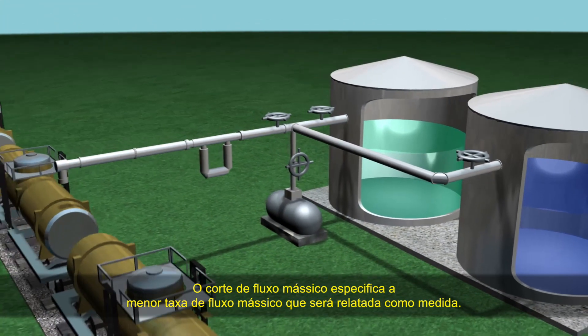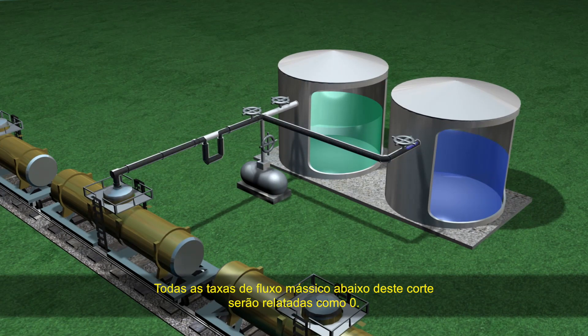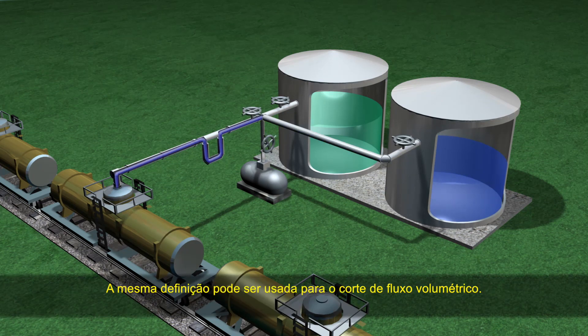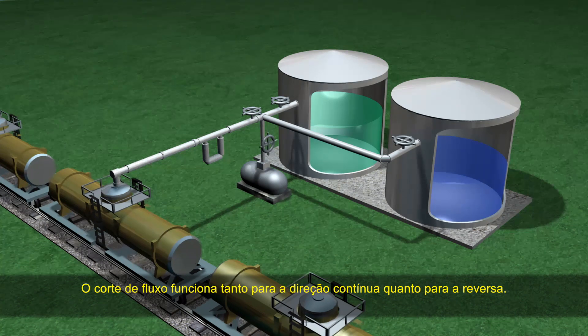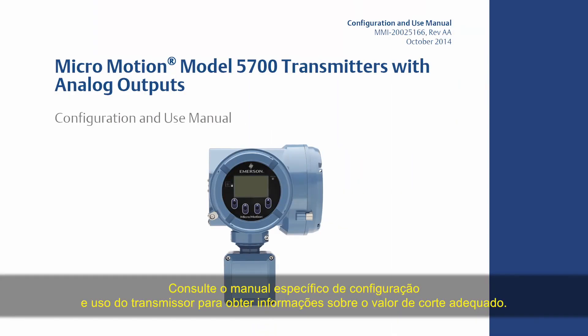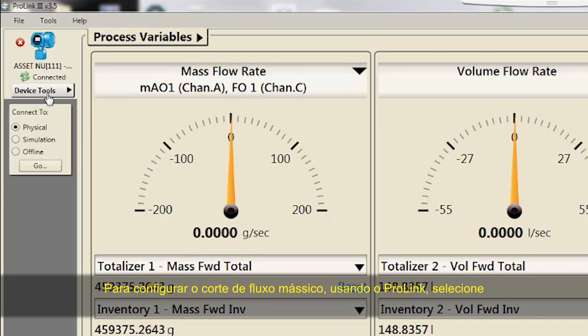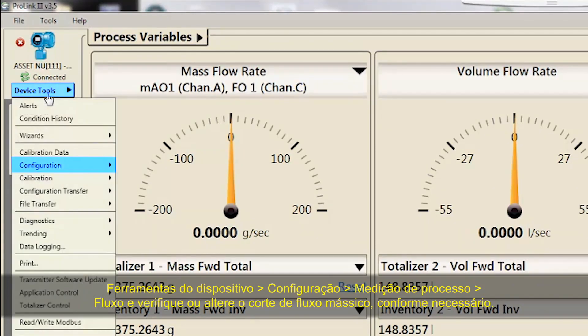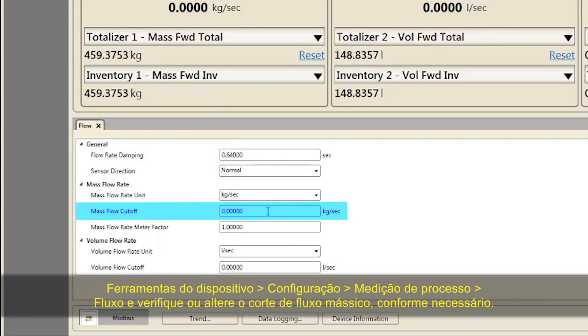Mass Flow Cutoff specifies the lowest mass flow rate that will be reported as measured. All mass flow rates below this cutoff will be reported as zero. The same definition can be used for volume flow cutoff. Flow cutoff works in both the forward and reverse direction. The mass flow cutoff should never be set to zero. Refer to your specific transmitter configuration and use manual for the proper cutoff value. For configuring mass flow cutoff using ProLink, select Device Tools, Configuration, Process Measurement, Flow, and verify or change the mass flow cutoff as necessary.